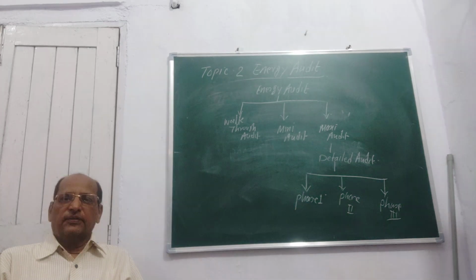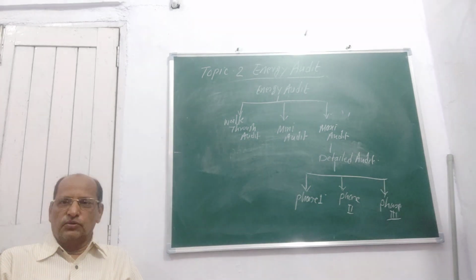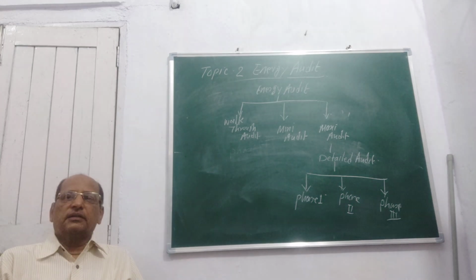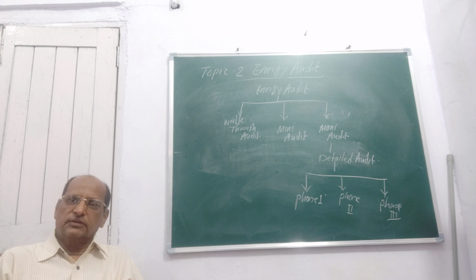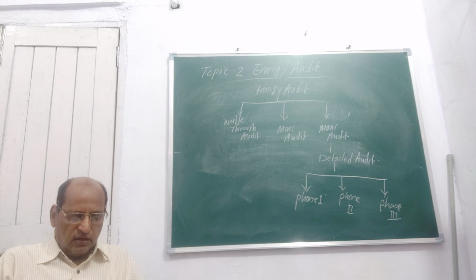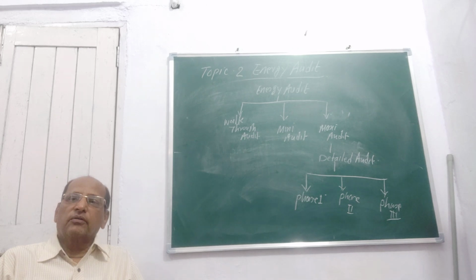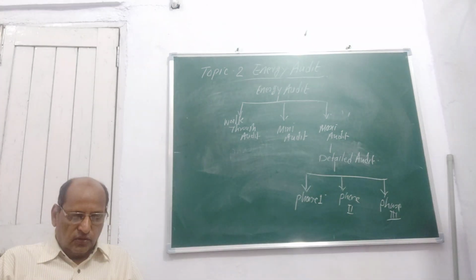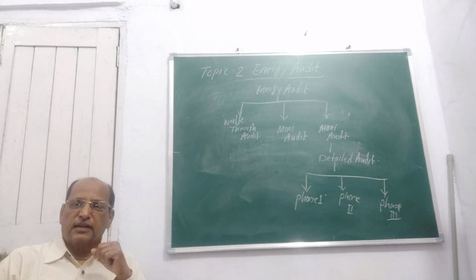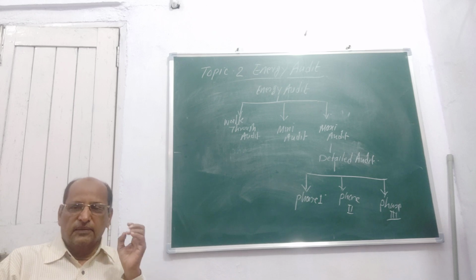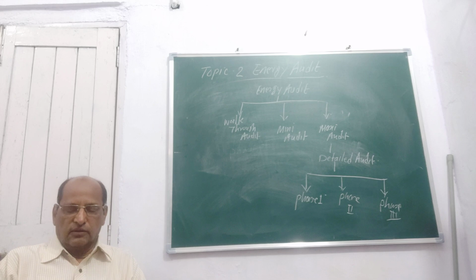This type of audit is basically applicable when electricity is used. And if you have an installation in which other forms of energy are used, then in that case you have to consider those particular types of energy and their parameters. Then when you list out all the loads and calculate their standard consumption, you have to quantify the energy used for each load and then sum up all these. So you will get the standard data for that particular installation, which is according to a theoretical calculation.